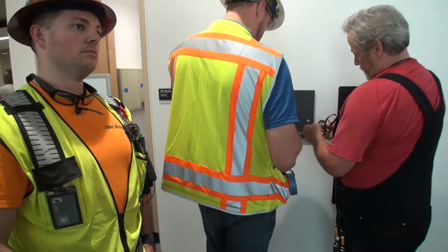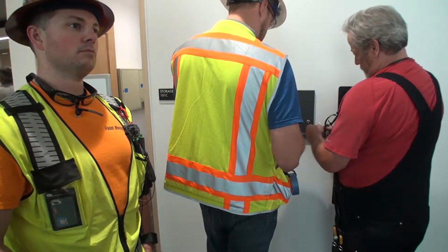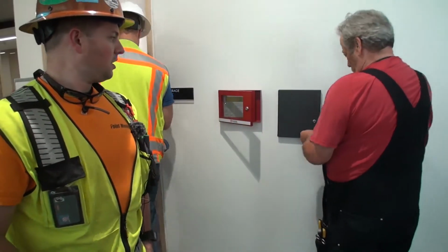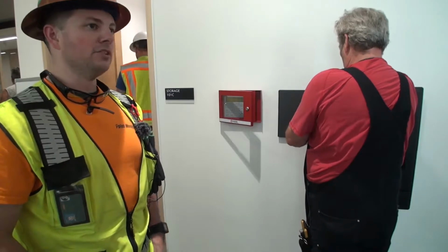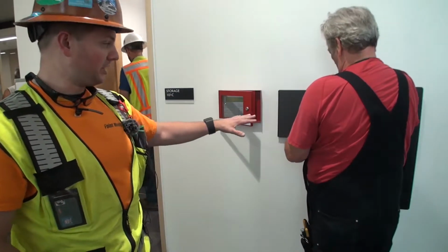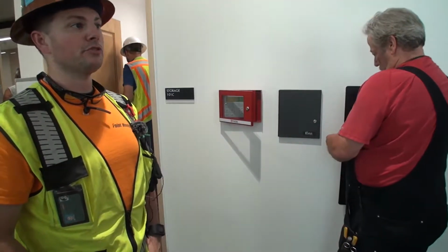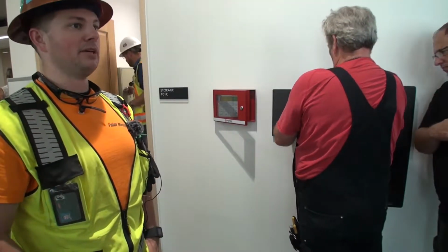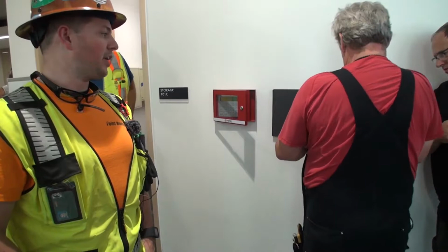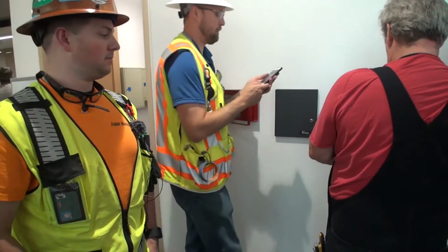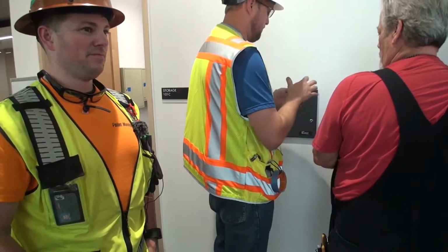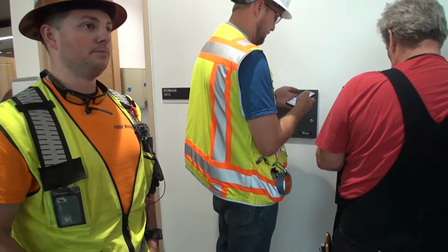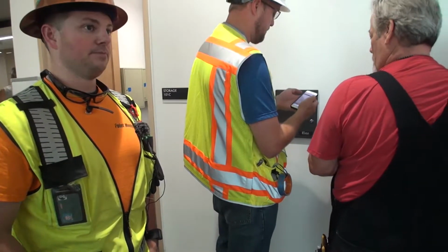And the auxiliary panels, are those basically like in the HDS? Yes. Or HDS, they're both. In those panels, aside from the main fire panel with the main voice panel, there's no user functions on any of them. They all just work automatically based on programming and wiring. And they all have battery backup. Their location will display with any issues on the main fire panel. And so they are in the MDFs and HDFs and all that stuff.